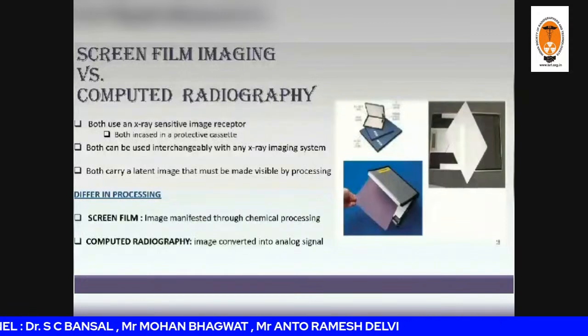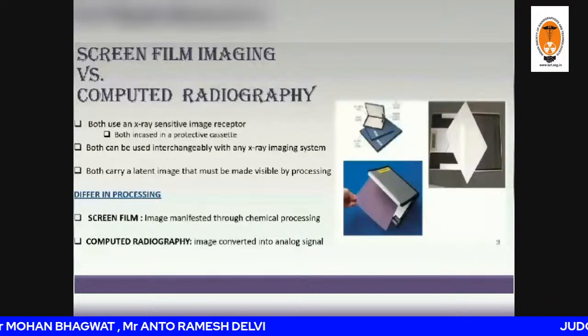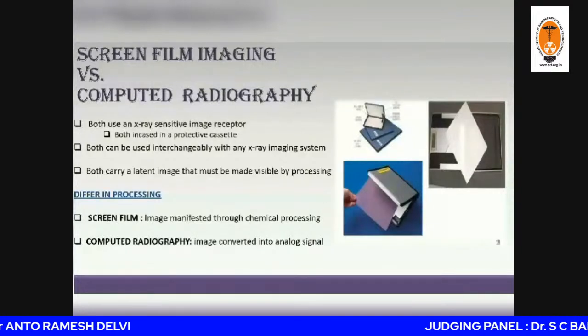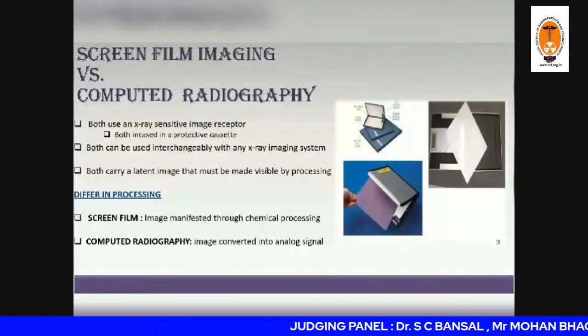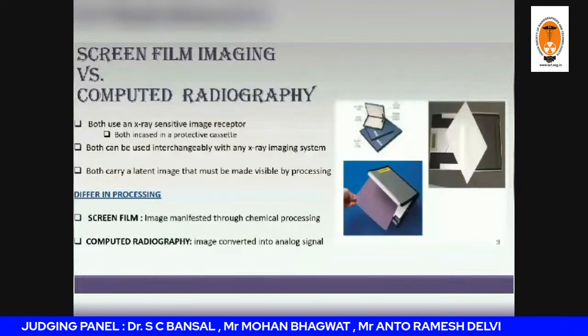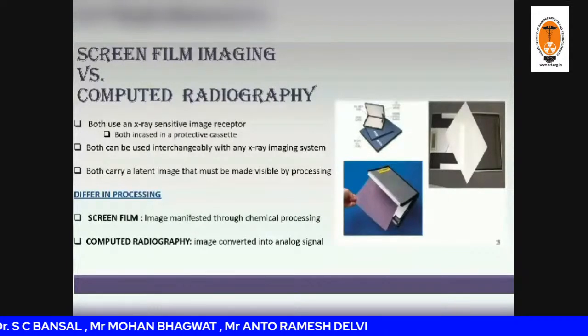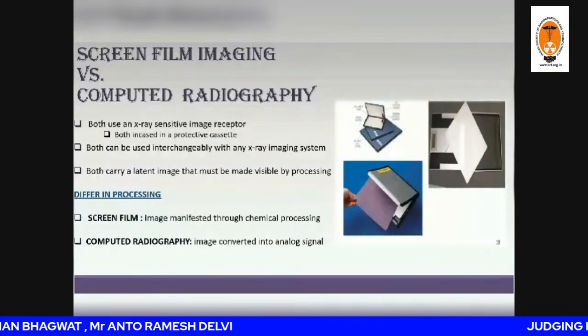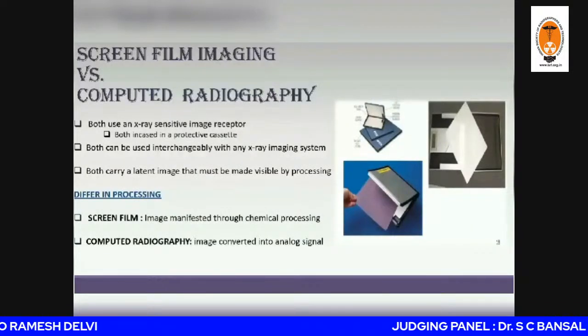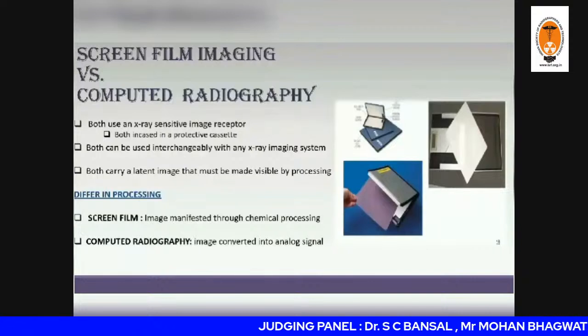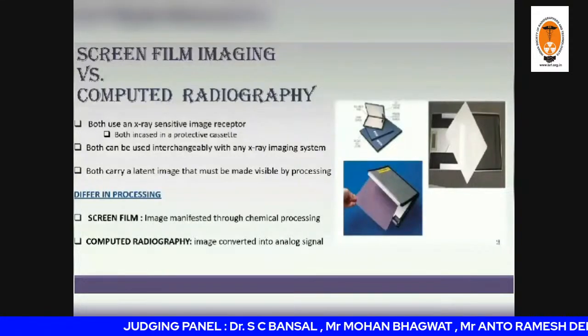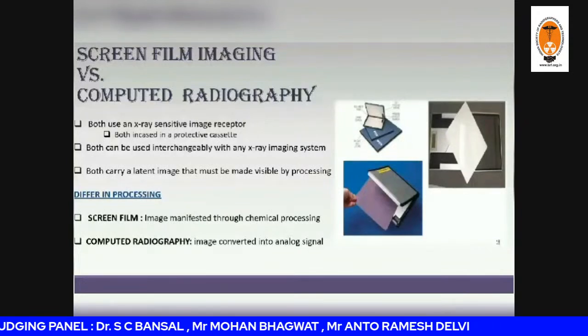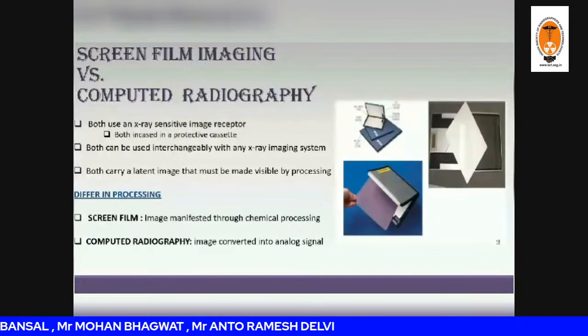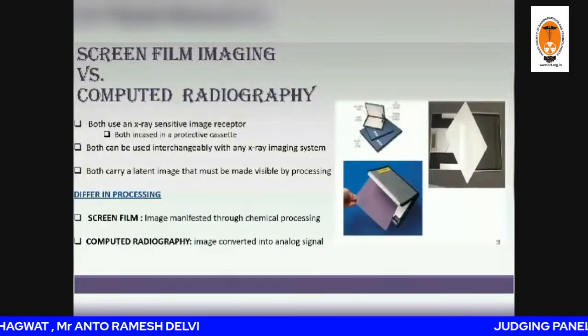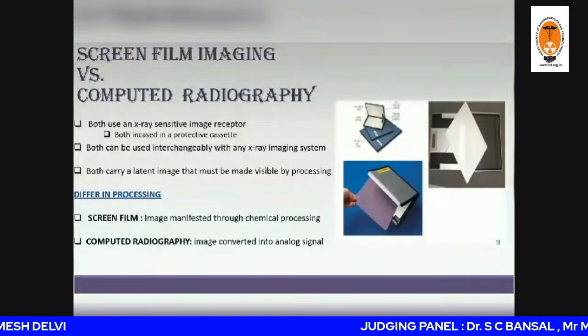Both screen film imaging and computed radiography use an X-ray sensitive image receptor. In screen film radiography, we see films inside the cassette, and in computed radiography, we see PSP screens inside the cassette. Both are encased in a protective cassette, and both can be used interchangeably with any X-ray imaging system. That means we don't have to exchange or refurbish our X-ray rooms. We can use the same equipment. The only difference is how the images are extracted. And both carry a latent image that must be made visible by processing.